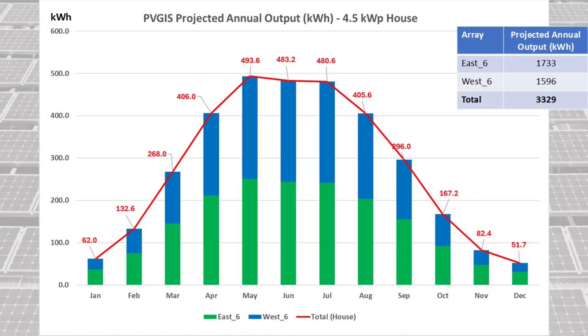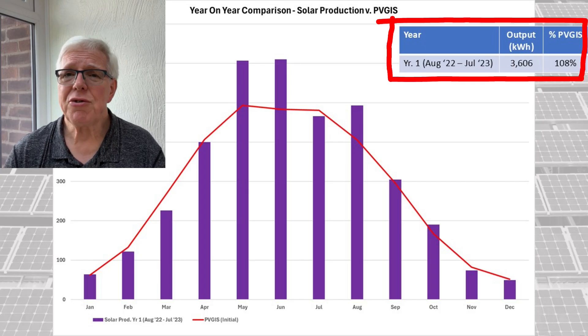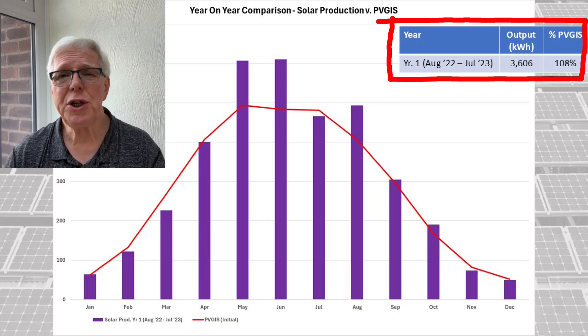Using the PVGIS tool, the projected annual output for our 4.5kW peak panel array came out at 3,329 kWh, with the east facing bank generating slightly more than the west facing bank. Taking the first 12 month period — August 2022 to July 2023 — we generated 3,606 kWh, which is about 8% more than the PVGIS projection.